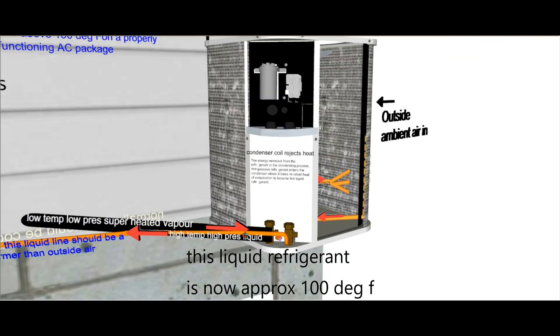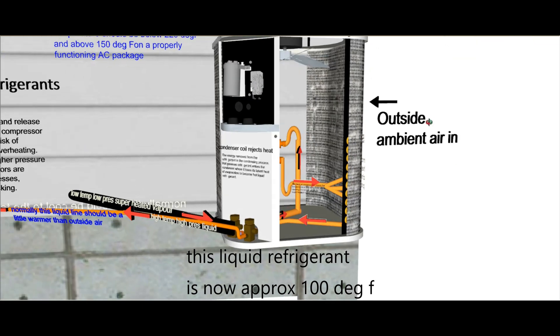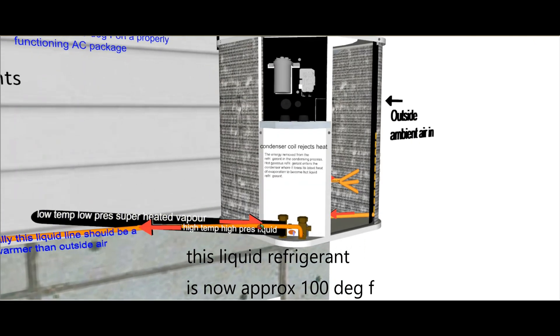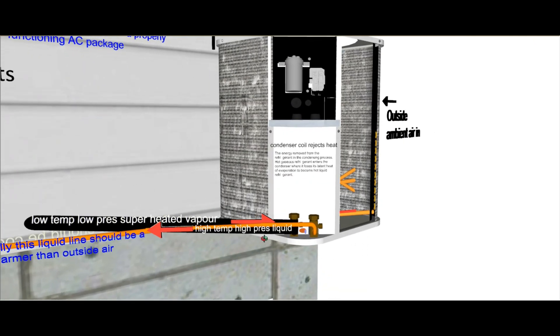Now generally speaking, this high temperature, high pressure liquid is around 20 degrees warmer than the outside ambient air. So this was 80 degrees Fahrenheit, this is about 100 degrees Fahrenheit, so it's warm to the touch. Right? So it's not cool, it's still warm, and now it's a liquid. So now it's going to go all the way back to the evaporator in the house.